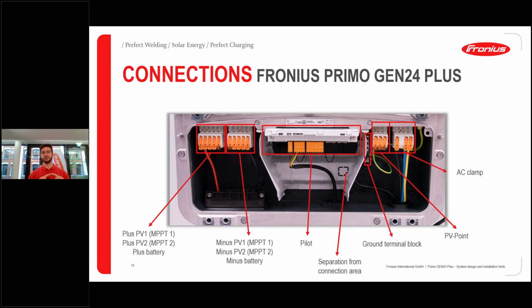We usually have there a black cover. Maybe you remember it from the previous slides. And we just undo this cover with 5 quick lock screws, and then we can directly see into this mounting area, in this installation area. Yeah, and from left to right, we can see here the DC side, both for plus and minus. They have individual mounting clamps. This is this DC terminal for plus and minus.